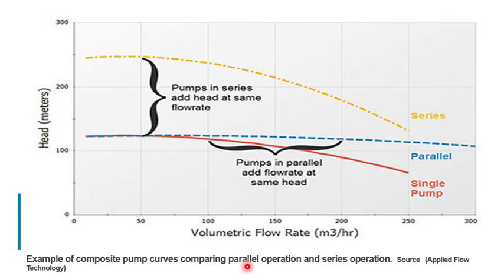So as we see here, this is an example of a composite pump curve comparing parallel operation and series operation, the source from the Applied Flow Technology website. So this is the configuration of series, and this is the configuration of parallel. We can see the difference: in series, it is going to the higher pump head, pumping system head, but in the parallel it will go to the higher volumetric flow rate in the system.